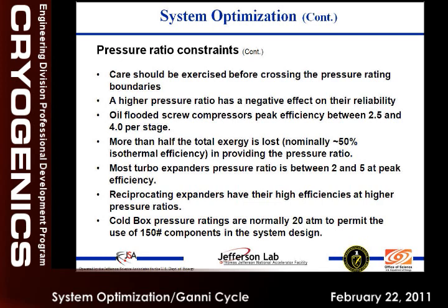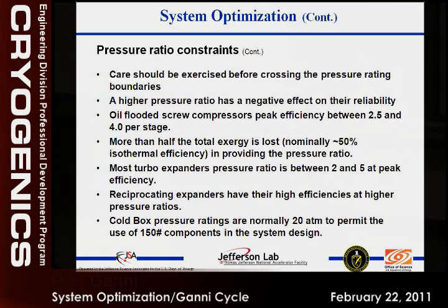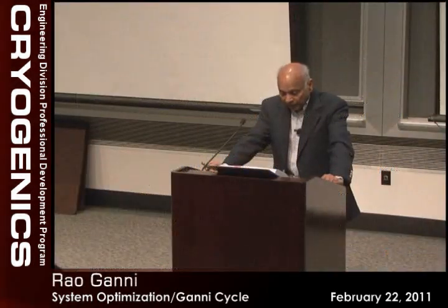After that, at least half is useful, half is lost in the cold box, and the other half goes into the load. But we lose most, two-thirds of our input power, at the compressor level in the losses. And it did not get the attention it deserves so far. That's one of the areas we want to put some time into, improving that efficiency and others.